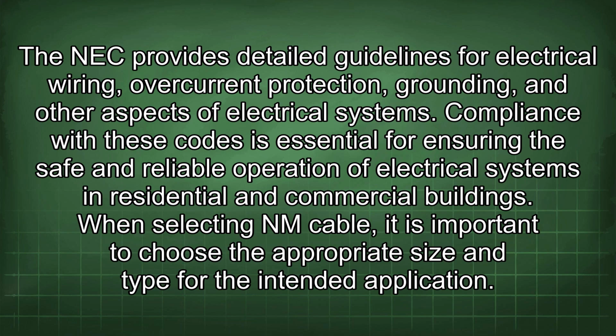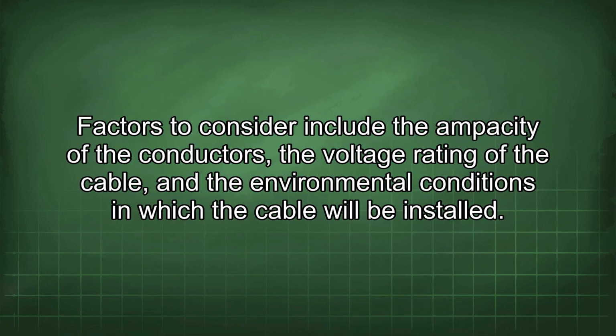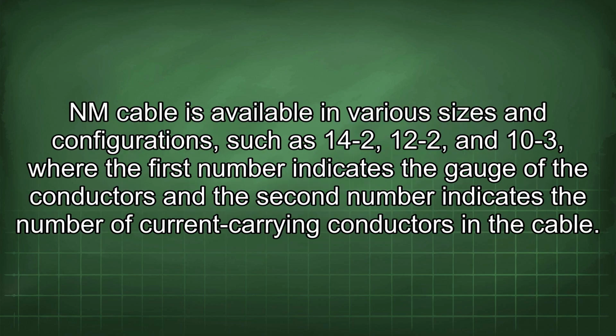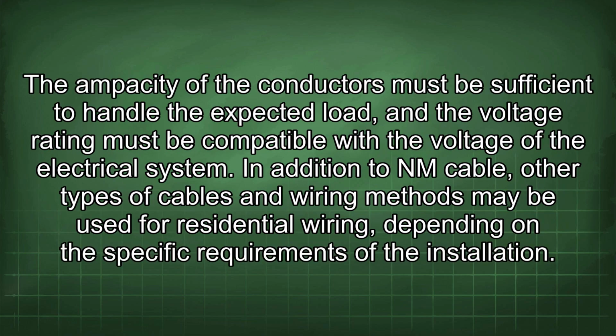When selecting NM cable, it is important to choose the appropriate size and type for the intended application. Factors to consider include the ampacity of the conductors, the voltage rating of the cable, and the environmental conditions in which the cable will be installed. NM cable is available in various sizes and configurations such as 14-2, 12-2, and 10-3, where the first number indicates the gauge of the conductors and the second number indicates the number of current carrying conductors in the cable. The ampacity of the conductors must be sufficient to handle the expected load, and the voltage rating must be compatible with the voltage of the electrical system.